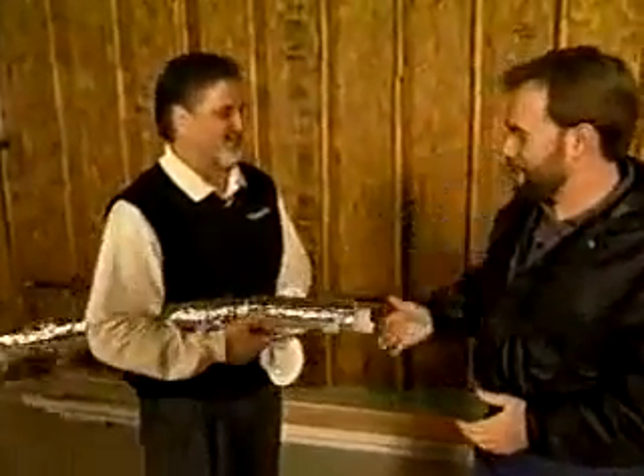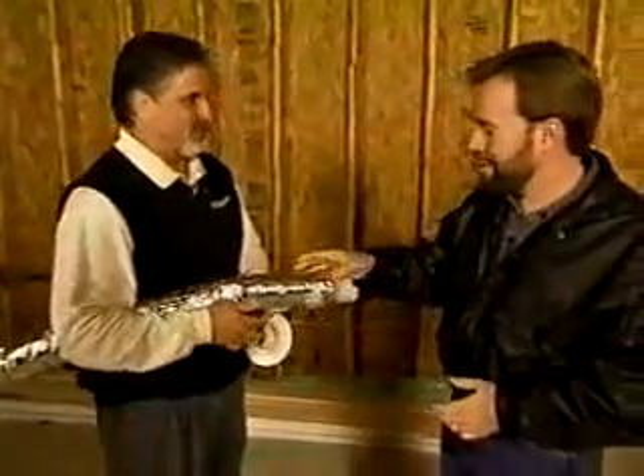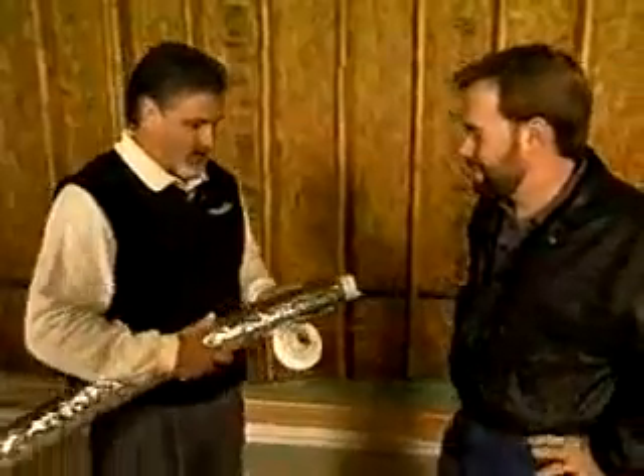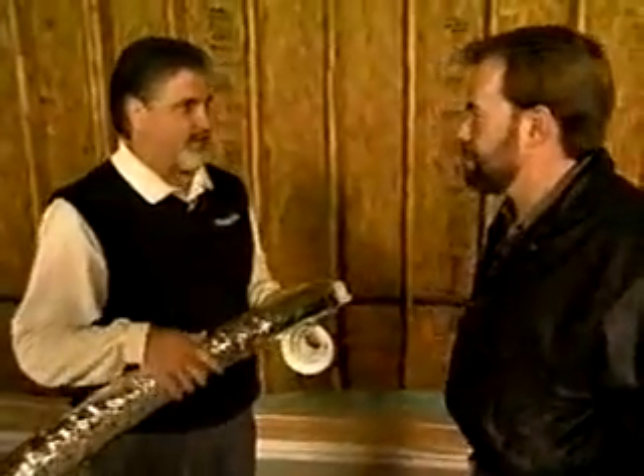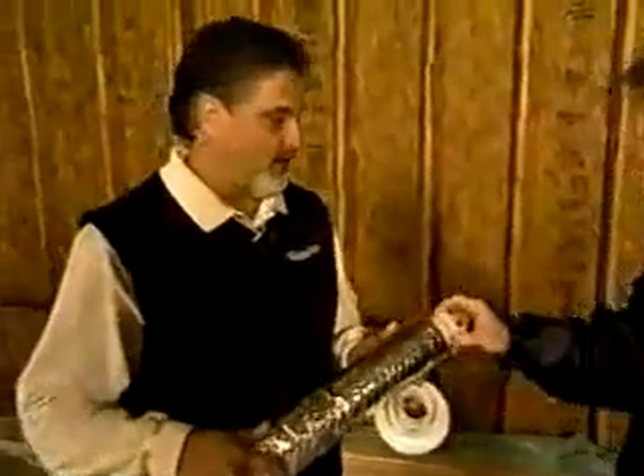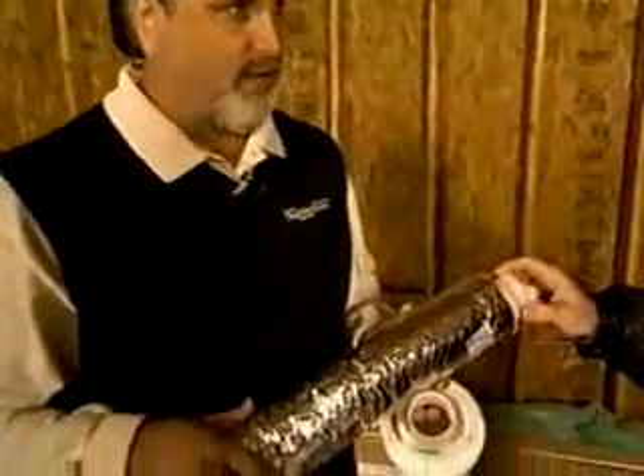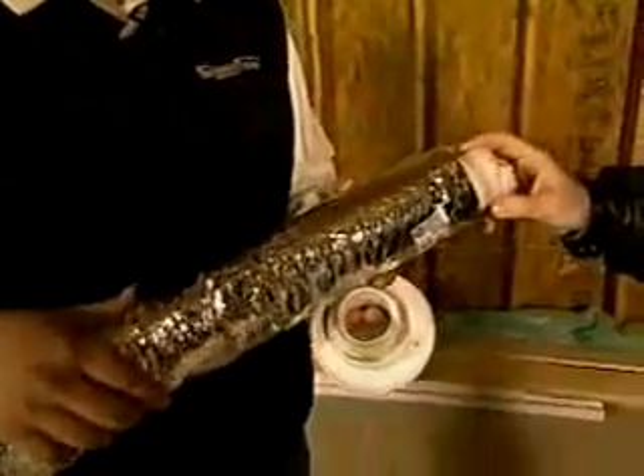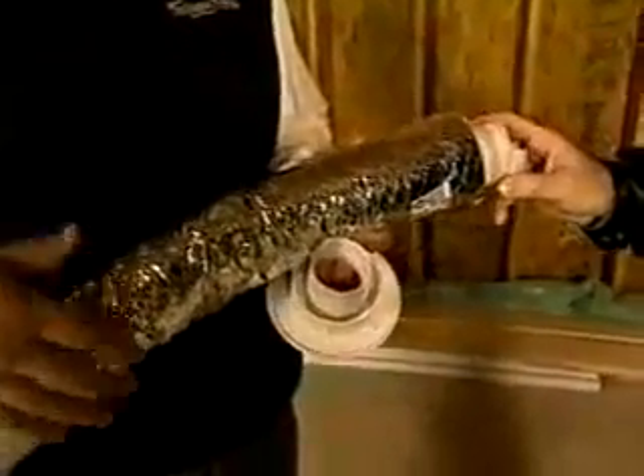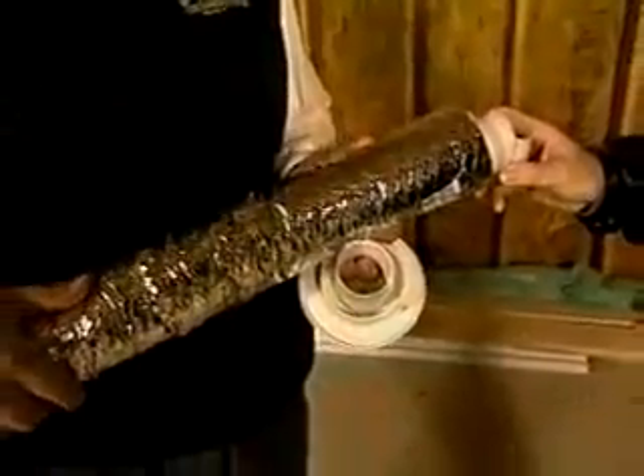Now, normally when you carry a piece of ductwork, it's like this, under your arm. Now you've got this. Tell me about it, why is it smaller and how does it work? It's a 2-inch diameter tube, 3.5 inches on the outside. Unico is a mini duct high-velocity pressurized system, which means we're pressurizing the duct and our velocities are higher in the ductwork. So you're pushing more air through a smaller duct.